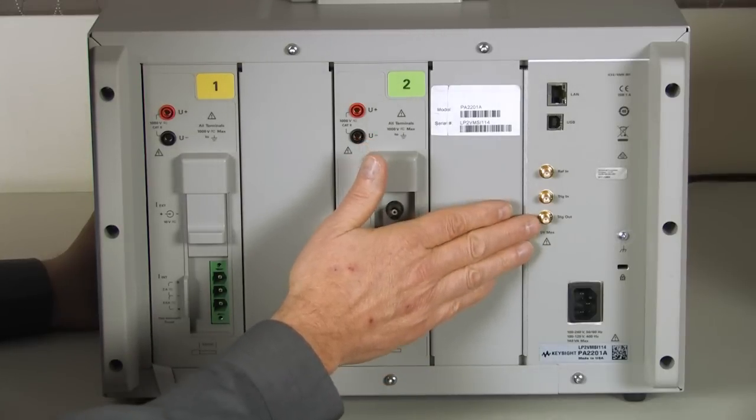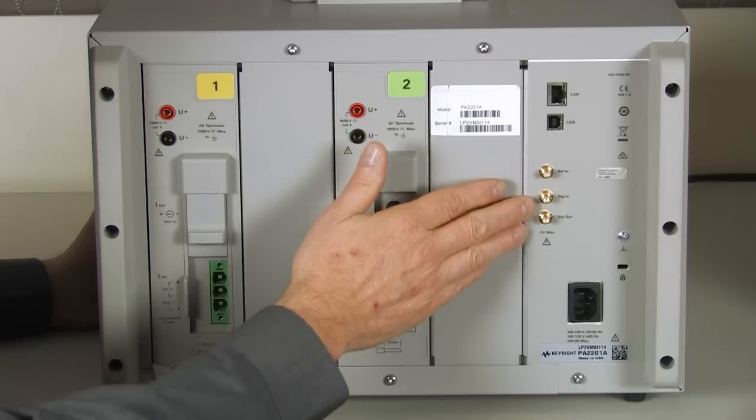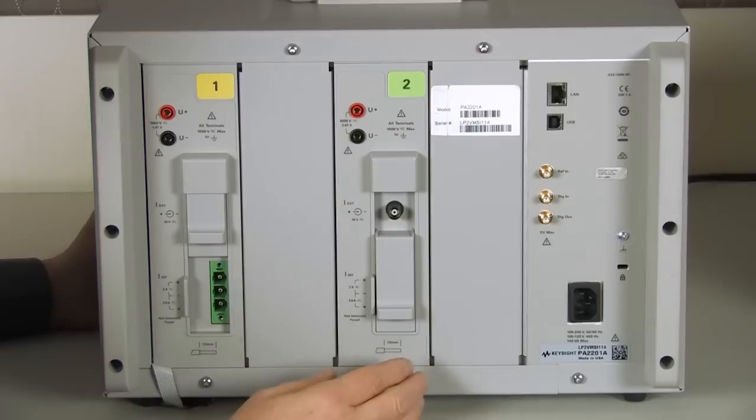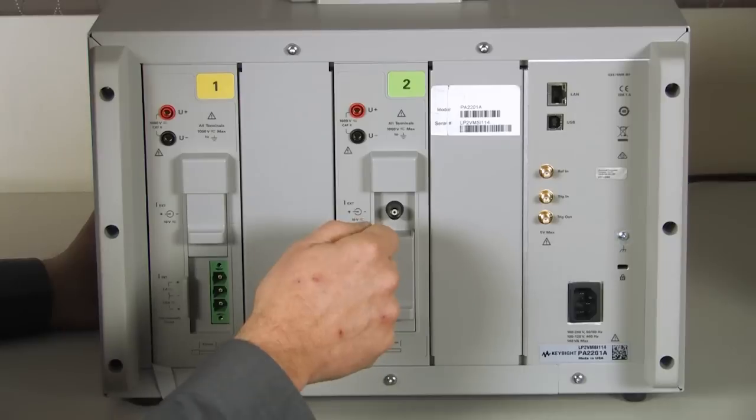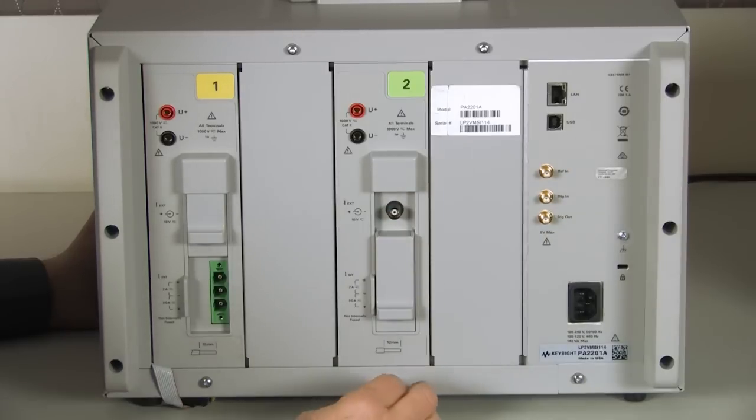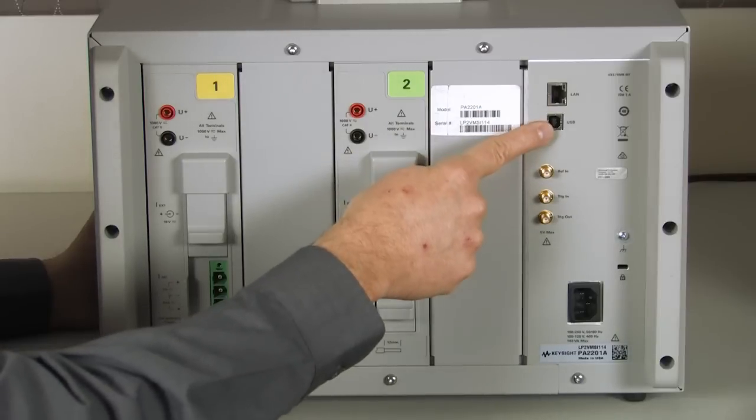And then as we circle around, we have both a trigger in, trigger out, and a 10 megahertz clock signal. All of these are with an SMA connector. We deliberately made these different than the BNC connector so that you can't mistakenly connect a BNC to one of these other signals. And then finally, we have a LAN connection and a USB connection.